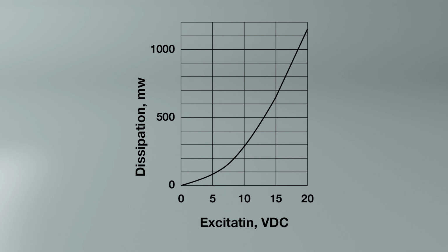Variation in excitation voltage can also cause a small shift in zero balance and creep. This effect is most noticeable when the excitation voltage is first initiated. The obvious solution for this effect is to allow the load cell to stabilize by operating it with 10 VDC excitation for the time required for the gauge temperatures to reach equilibrium. For critical calibrations, this may require up to 30 minutes.